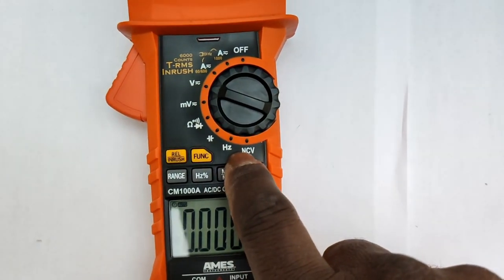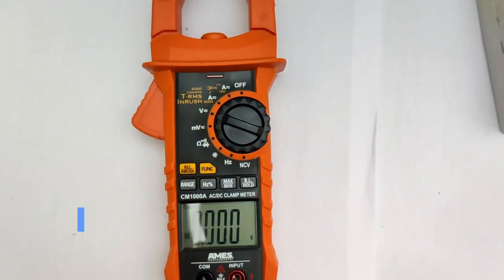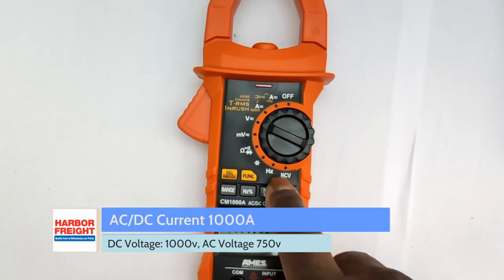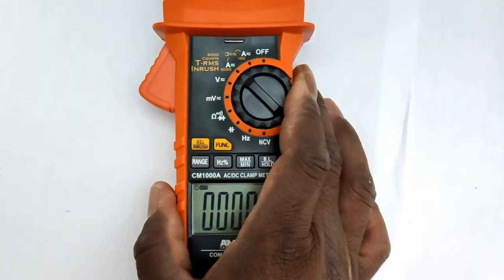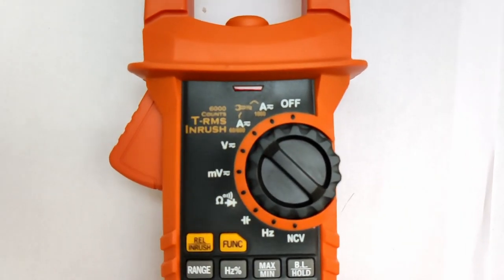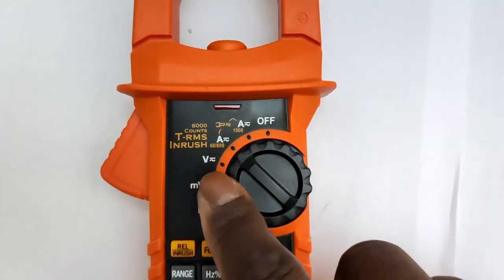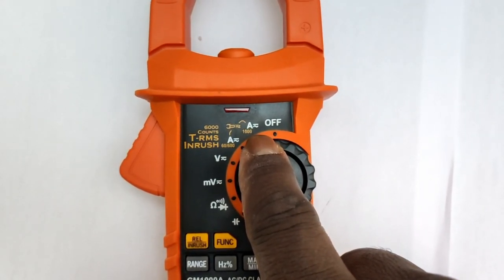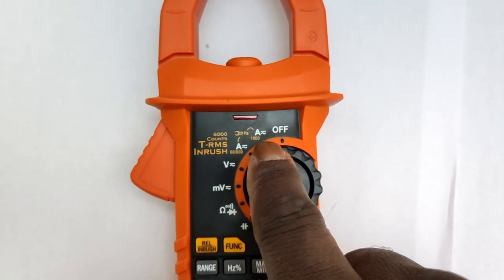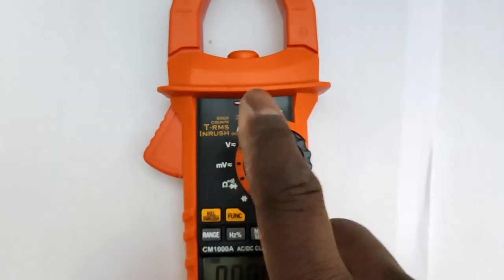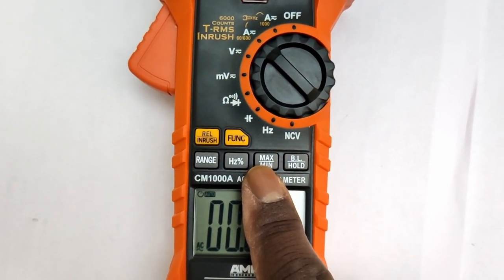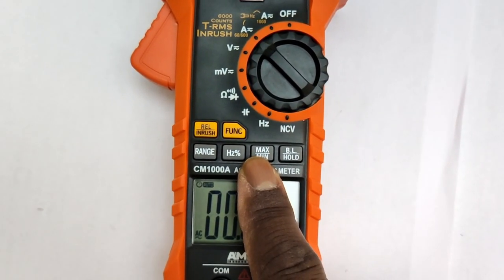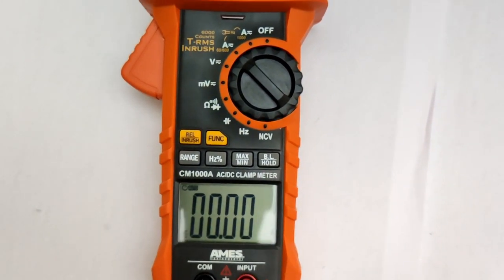In case you guys are wondering what all it can do, it does frequency, it does non-contact voltage. But the functions we're going to be using it for are amperes. You got an auto mode that can measure 600 amperes, and then you got a high amper mode that measures anything up to 1,000 amps. I'm going to put it on auto, and then use the max min feature to let us know what our maximum current draw is.